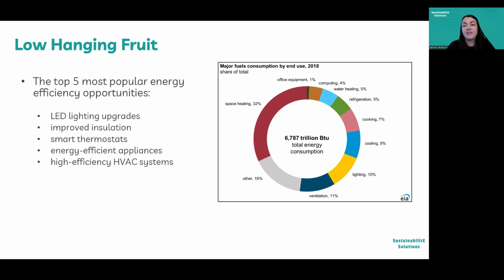The top 5 energy efficiency opportunities I see are LED and lighting upgrades, improved insulation—working on your building envelope or even new windows if it's a historic building—and really getting into HVAC tune-ups, duct sealing if it leaks, putting in deadbands so you're not fluctuating as much. Depending on the size of your facility, they may recommend variable frequency drives, so you're at a more stable level of HVAC rather than it heating and cooling all the time.